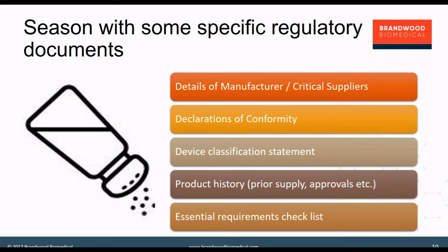And obviously, a very significant piece of information here, the essential requirement checklist. So if you're looking into the European requirements under the MDD, the essential principles would be collated into some kind of checklist. Under the new MDR, the terms have been changed and the requirements are now a bit more specific. They've been renamed as safety and performance requirements, but the process nonetheless remains the same.